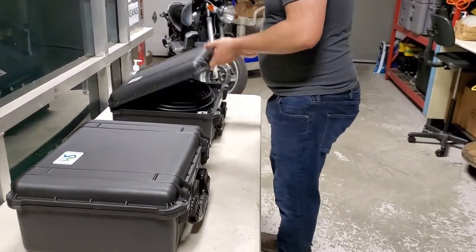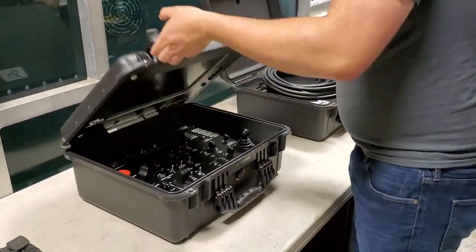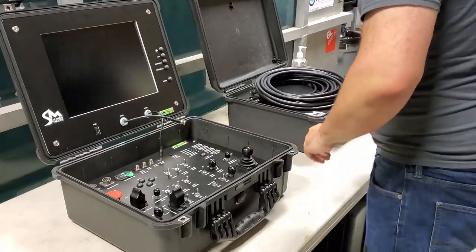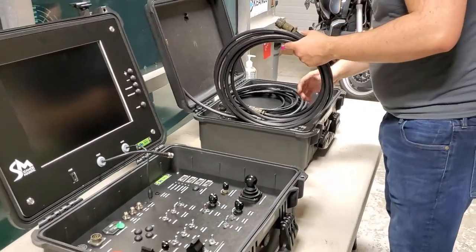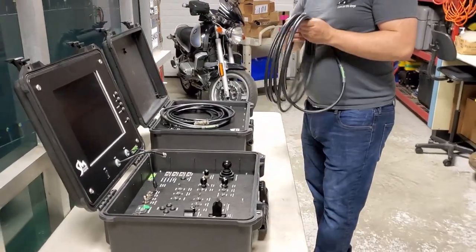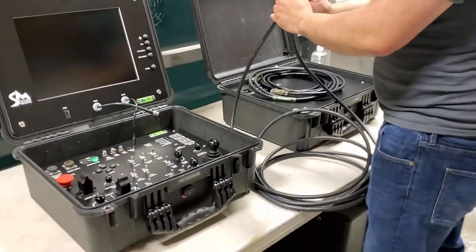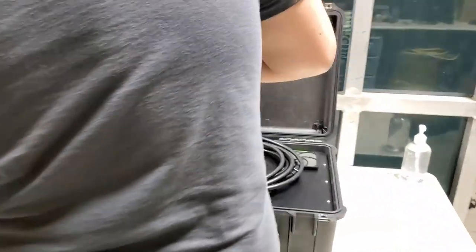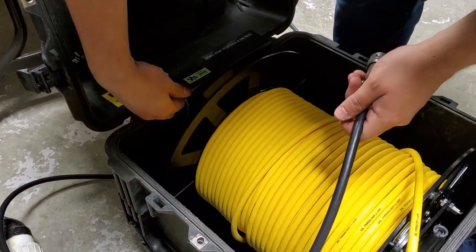Now, normally we keep the deck cable and the interconnect cable in the power supply unit. They may be somewhere else, depending on if the system has a second monitor. Check both ends of the cables before using them for any water or debris. These should be dry.